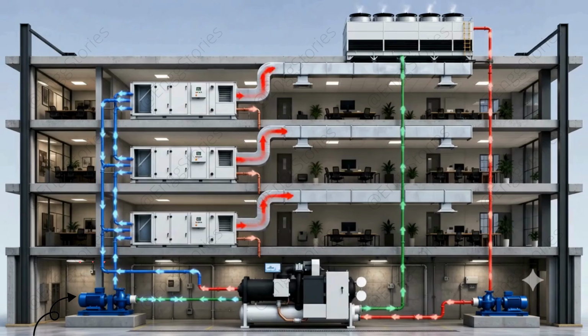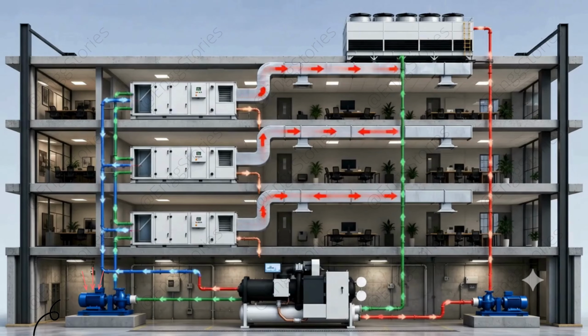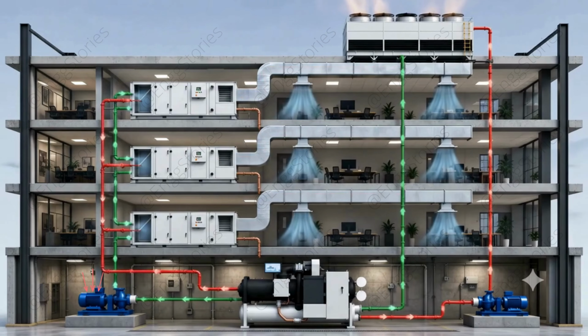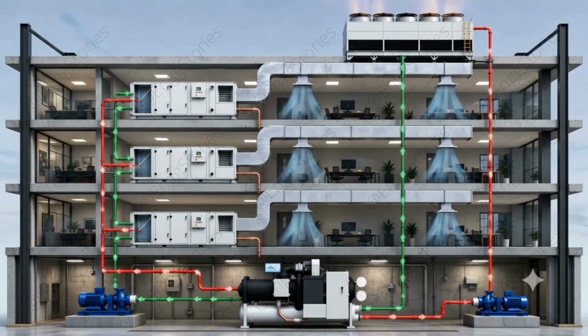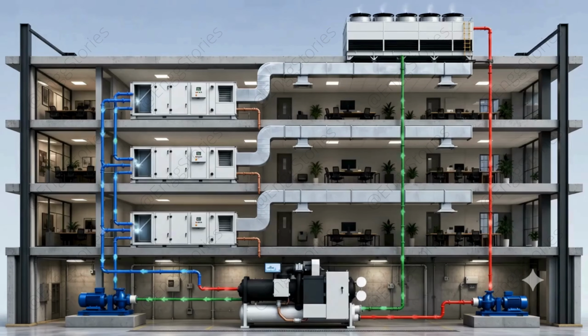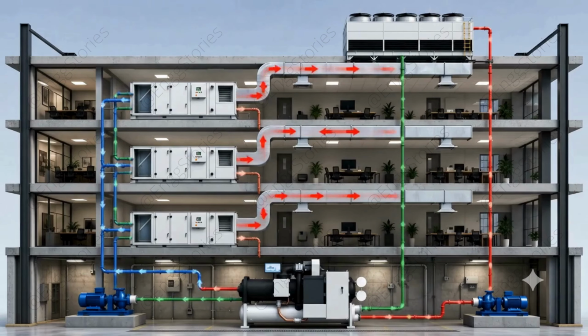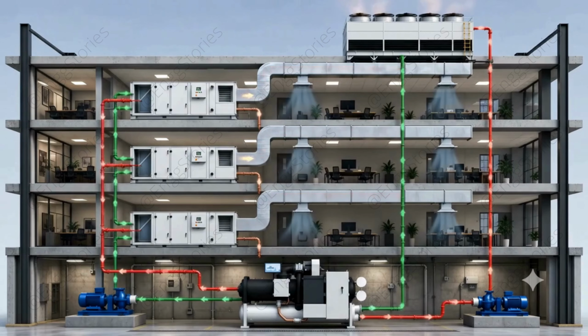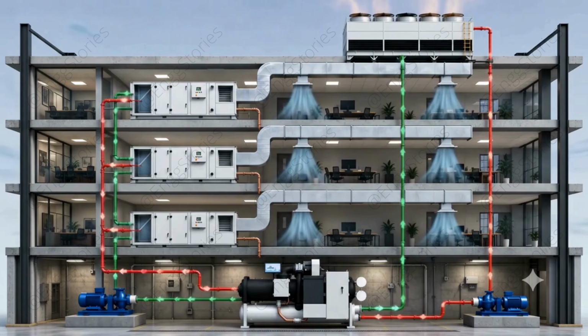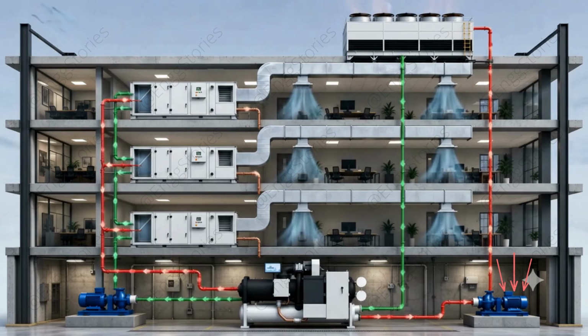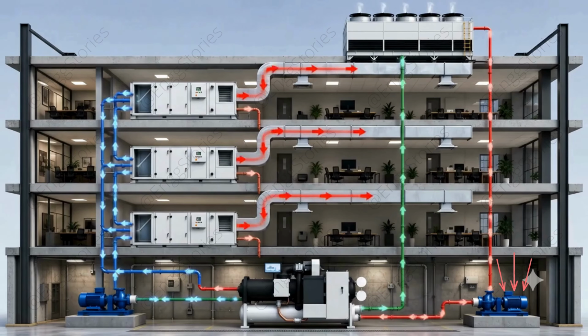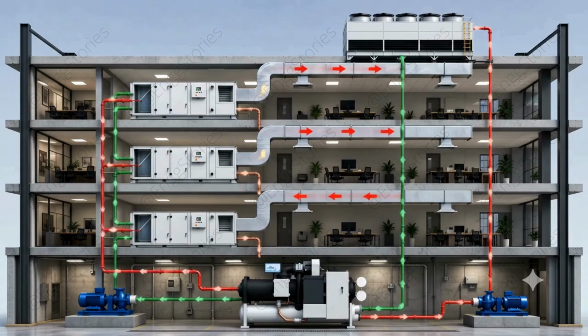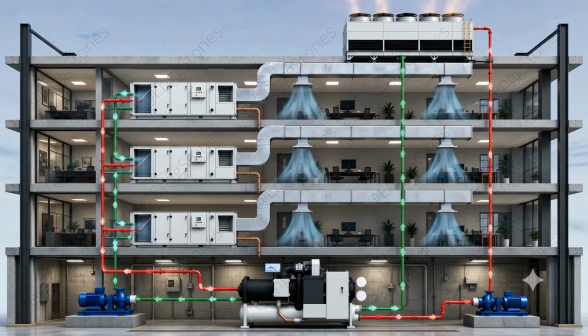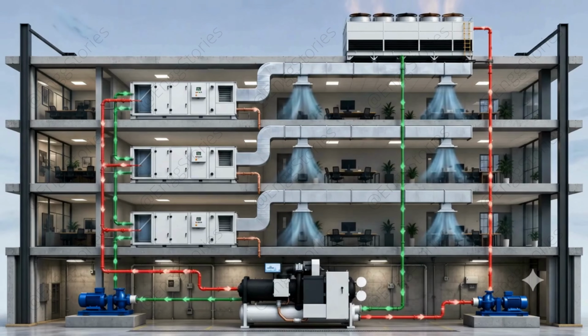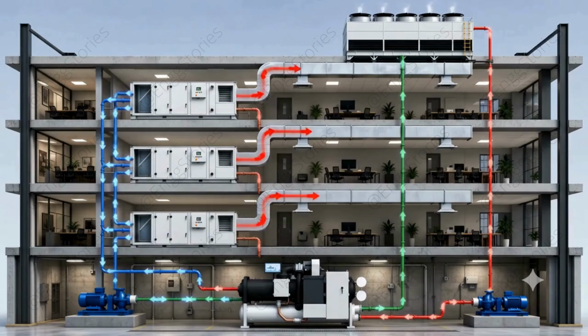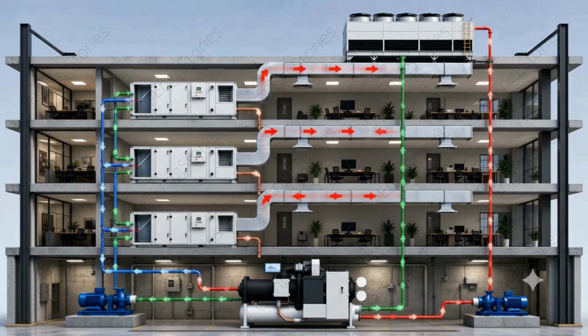The first is the chilled water primary pump. It circulates chilled water from the chiller's evaporator to the AHUs or fan coil units. As the chilled water absorbs heat from the building, it returns to the chiller to be cooled again. This cycle continues to provide comfortable indoor cooling. The second is the condenser water pump. Its job is to circulate water through the condenser. This water absorbs heat from the hot refrigerant inside the condenser and carries that heat to the cooling tower. In the cooling tower, the heat is released into the atmosphere, and the cooled water returns to the condenser to repeat the process.